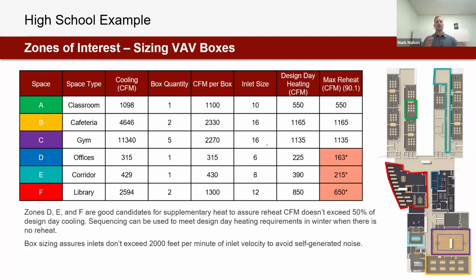And the first piece here would be actually sizing the single duct boxes. So if we look at a classroom, it's getting one VAV box. Its cooling CFM was about 1100 CFM, so we size a size 10-inch box for that. When we look at the cafeteria, it's needing 4600 CFM for cooling, so we're actually going to need two size 16-inch boxes in that case.